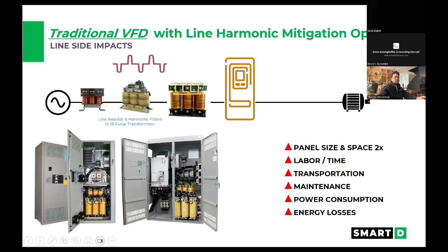All right, now we mentioned very briefly that other people have taken this active front end idea and they've tried to play with it. One of them, for example, is called a matrix drive. And in a matrix drive, there's no DC bus. And so it's a great experiment. It is basically a multi-pulse drive in a sense, but you're going to have a loss of voltage drop between the input versus the output. So you have a sizing issue. It's very sensitive to shock loading and things like that, and grid disturbances.